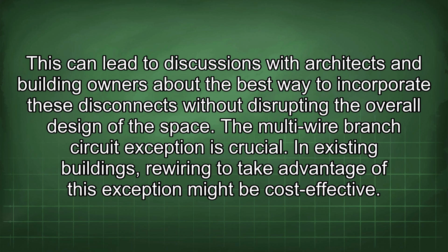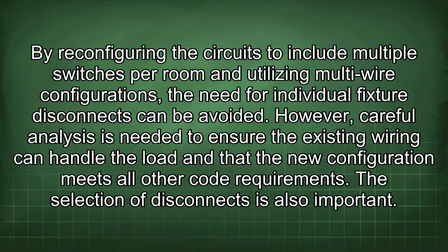The multi-wire branch circuit exception is crucial. In existing buildings, rewiring to take advantage of this exception might be cost-effective. By reconfiguring the circuits to include multiple switches per room and utilizing multi-wire configurations, the need for individual fixture disconnects can be avoided. However, careful analysis is needed to ensure the existing wiring can handle the load and that the new configuration meets all other code requirements.